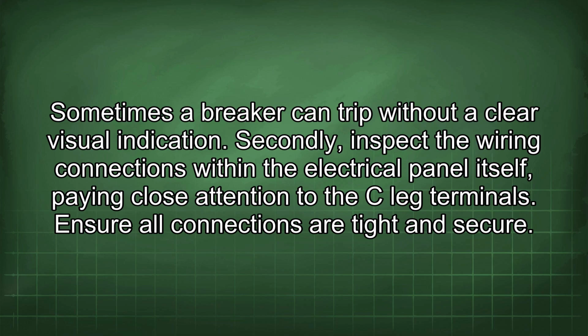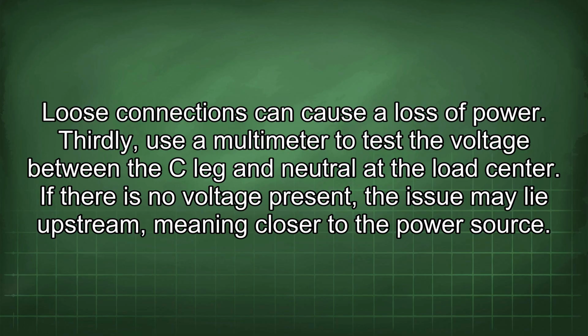Secondly, inspect the wiring connections within the electrical panel itself, paying close attention to the C-leg terminals. Ensure all connections are tight and secure. Loose connections can cause a loss of power. Thirdly, use a multimeter to test the voltage between the C-leg and neutral at the load center. If there is no voltage present, the issue may lie upstream, meaning closer to the power source.